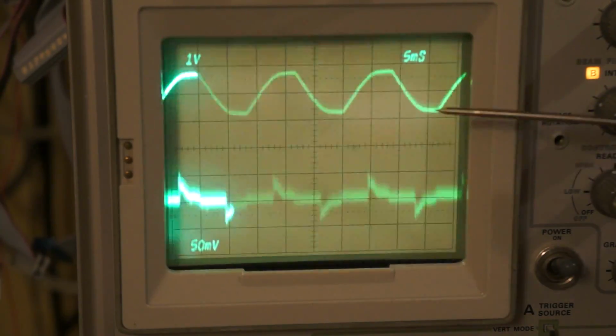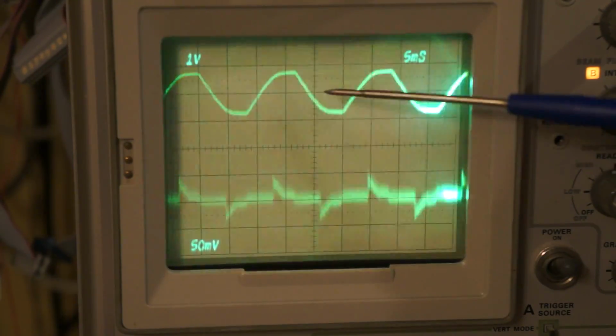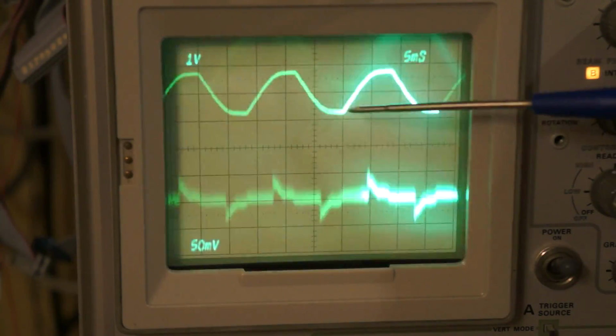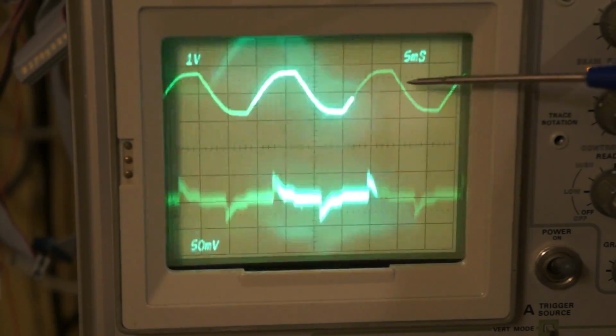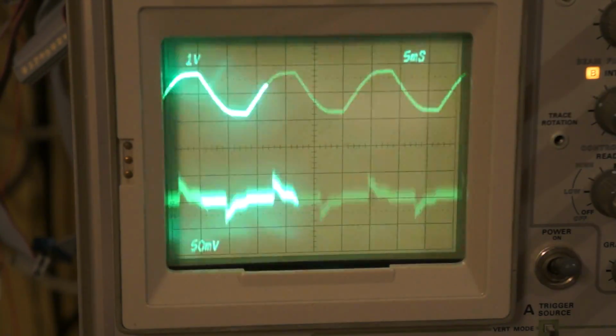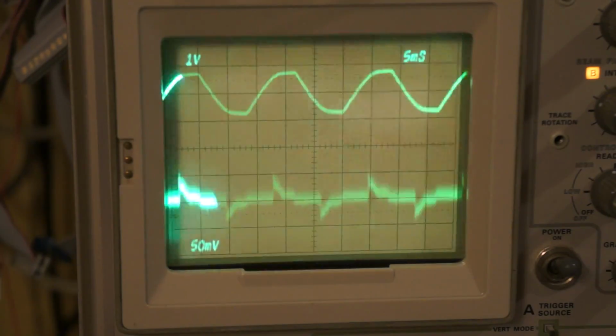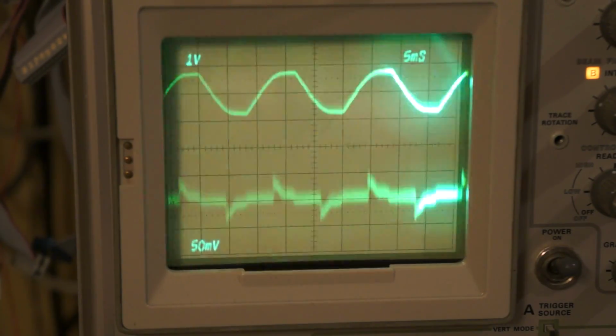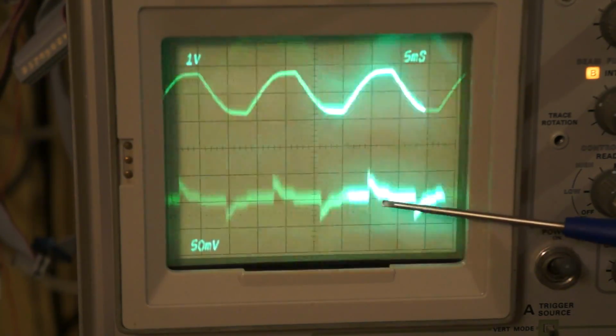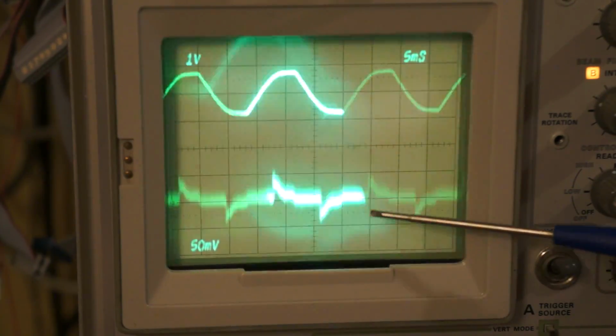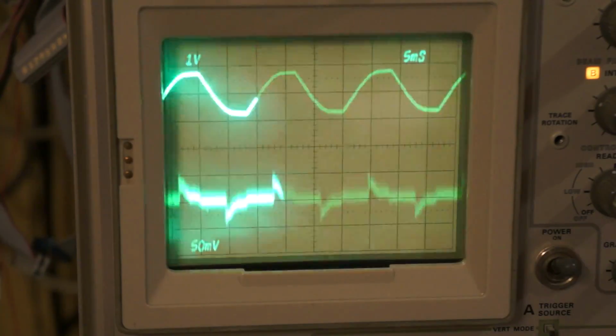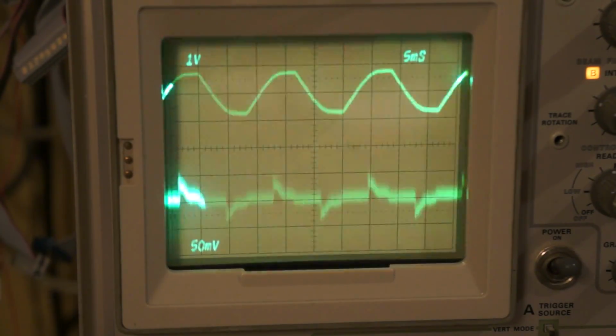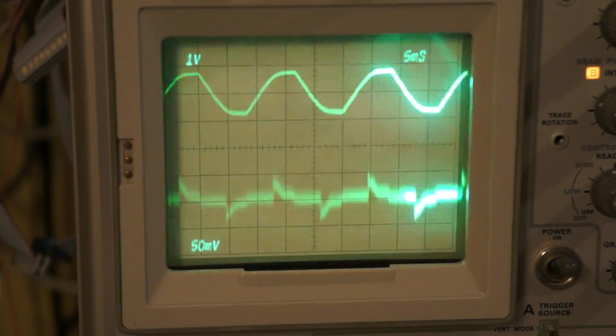In this situation we have voltage and current. I've confirmed that the voltage, theoretically a 60 Hz sine wave, is inordinately flat-topped. I haven't really determined what's causing that, but presumably way too many switching power supplies with shitty power factor correction. This here is the current waveform, and it really looks rather ghastly - this is a very, very shitty fluorescent that came with a $20 tensor lamp.